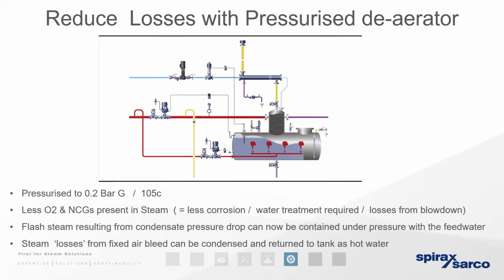So we've spoken about the benefits that we can enjoy by moving towards a system where we can keep the feed water under pressure in a pressurized deaerator. So if we're elevating the pressure to 0.2 bar gauge, we can elevate the temperature to 105 degrees or thereabouts. So we've got a significant number of benefits here. For one, a higher pressure equals a higher temperature, so the boiler is going to respond more rapidly whenever there's a demand for steam. For two, it means we're going to be placing less stress, less thermal fatigue, on the boiler if we're putting hot water into the boiler, as opposed to putting water that's slightly colder into the boiler.